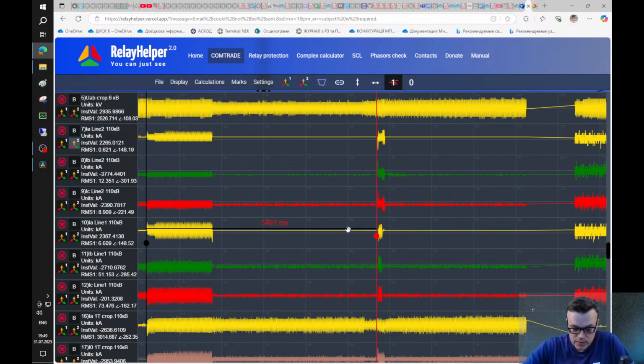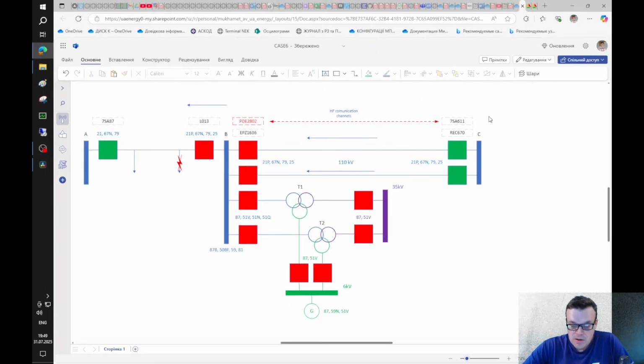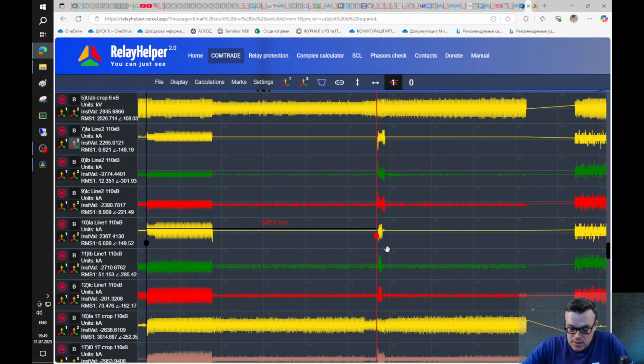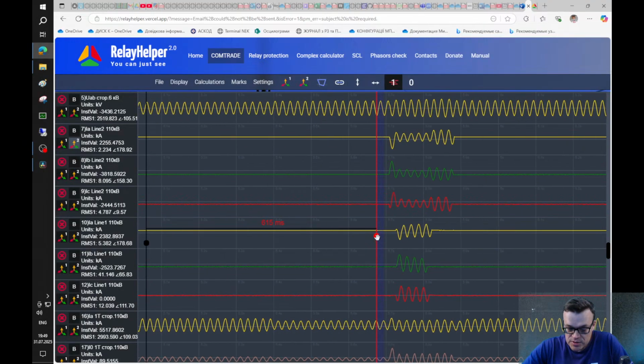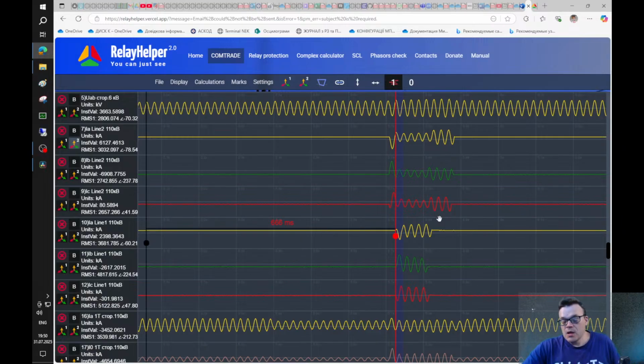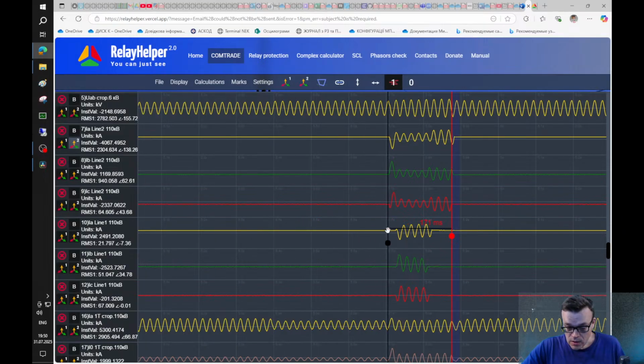So at this point, like the first 5 seconds, we have this picture, and here we see automatic reclosing. The first line, and then the second line, trip by SOTF functions. The first line tripped a little bit earlier, the second line a little bit later, about 170 milliseconds for the second line.